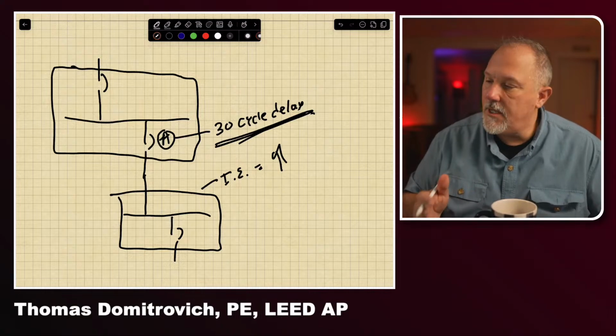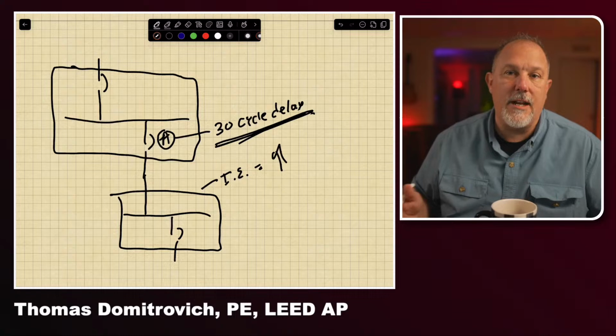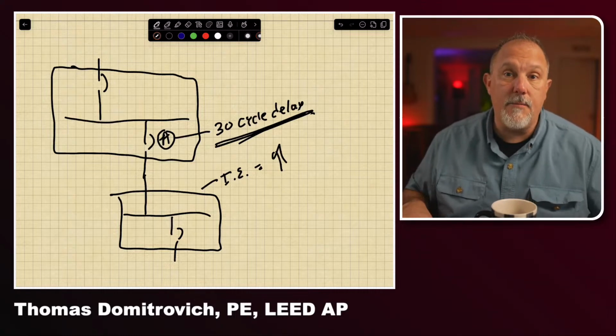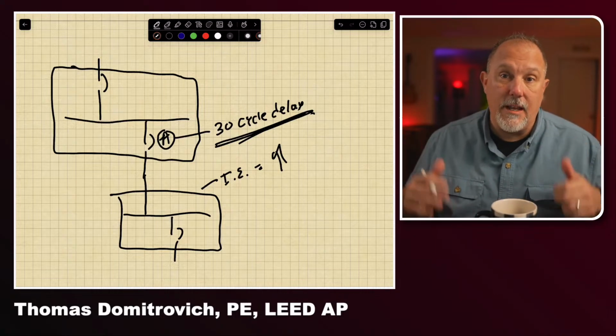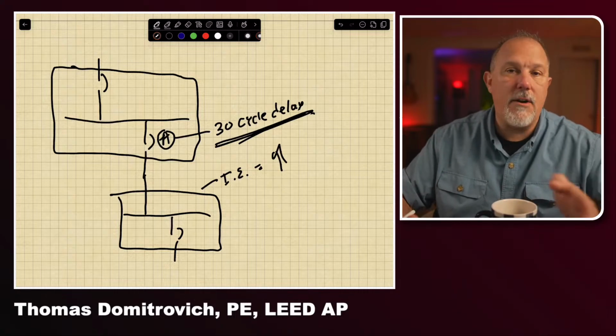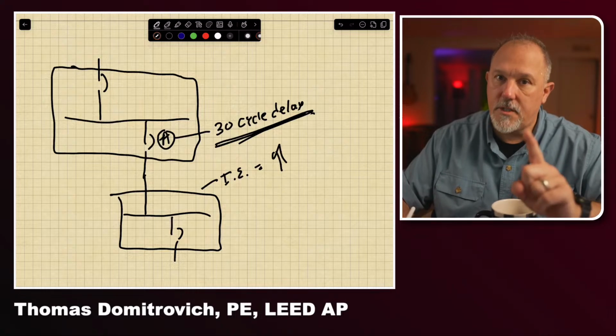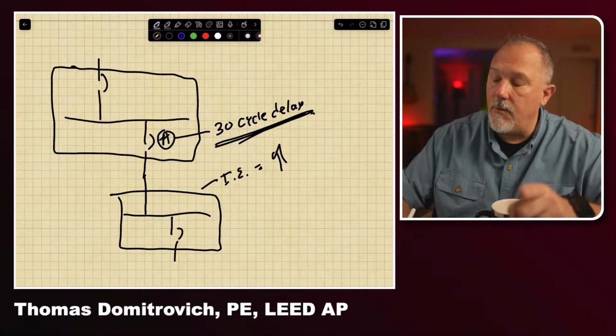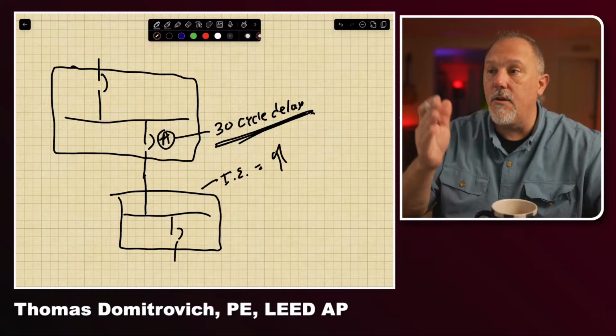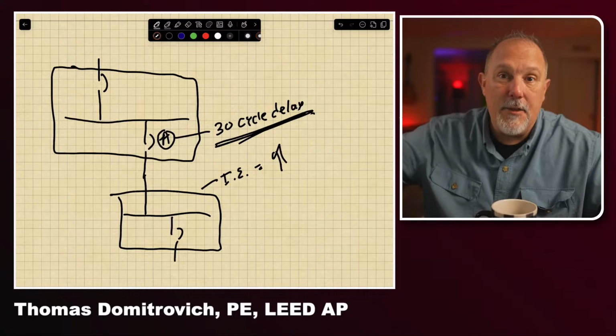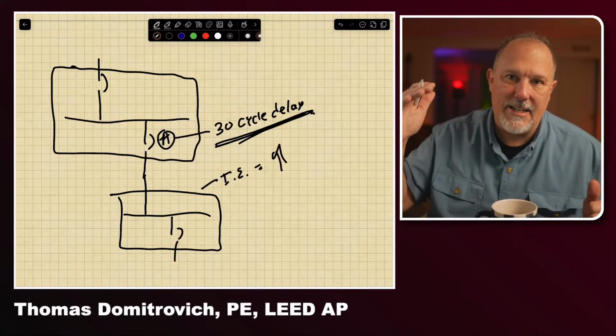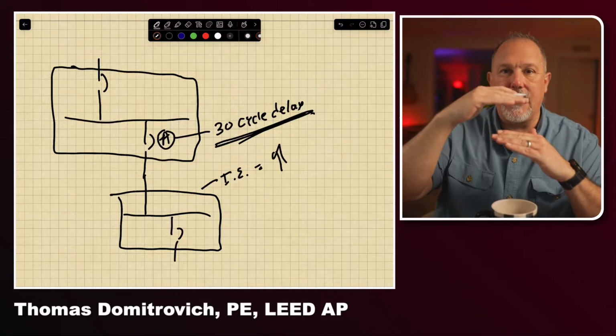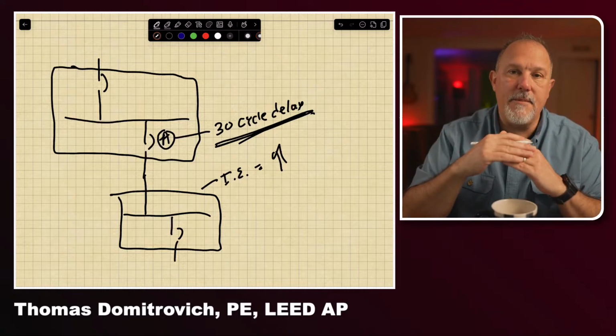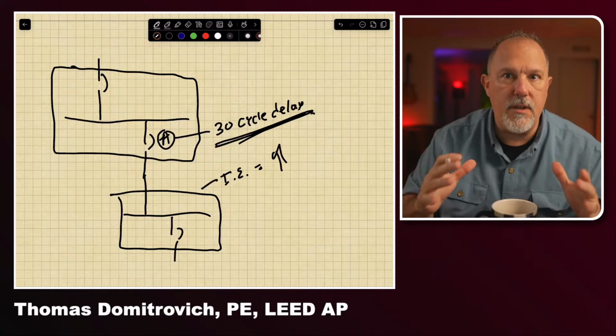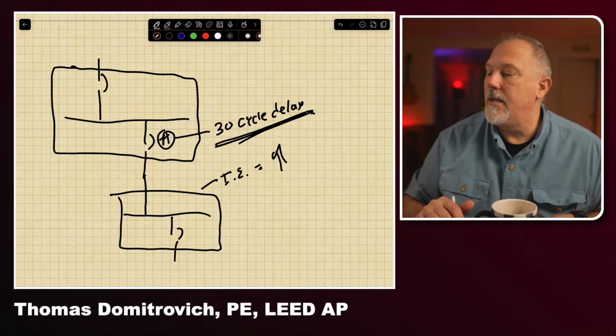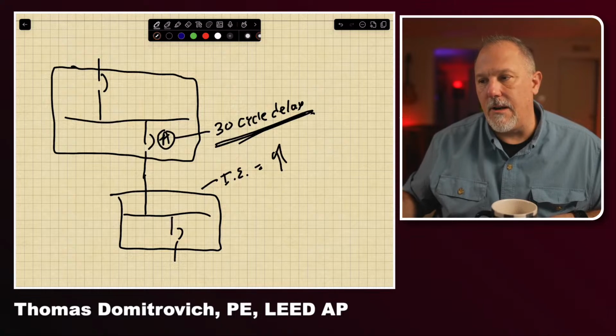So I couldn't understand, and I remember going out to Philadelphia and a few other locations, and I would teach this, and I would say, look, if you're going to selectively coordinate the system, you are going to drive higher incident energy values in the power distribution system because you're adding intentional delays. I may not have that same problem with fuses, but I will definitely have that problem with circuit breakers. If your available fault current is less than the instantaneous of the upstream breaker, then your arcing currents are definitely going to be less than the upstream instantaneous. And now on the shelf in the curve, if it's a 30 cycle delay, then you've got 30 cycles. So your clearing time depends upon the short time delay that you implement, if you even implement one. There's no requirement to implement one.